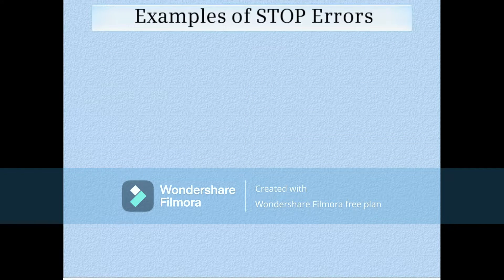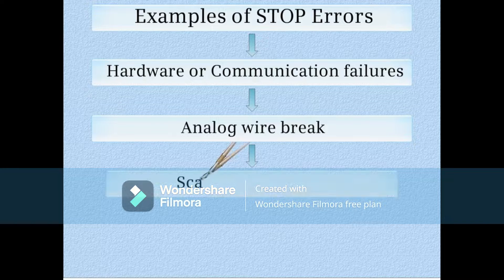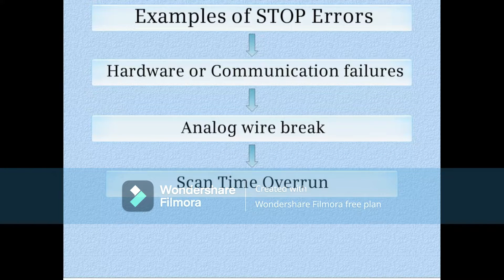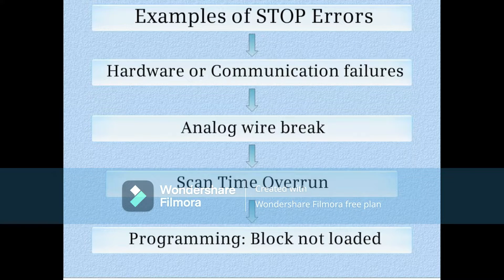The first category we will look at is stop errors. Some examples are hardware or communication failures, a wire break on an analog module, a program scan time overrun, or forgetting to download a block causing a block-not-loaded error.